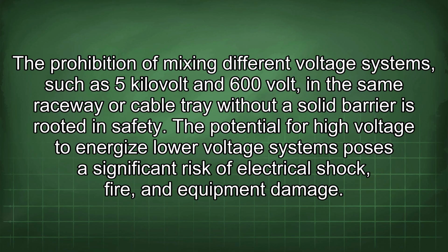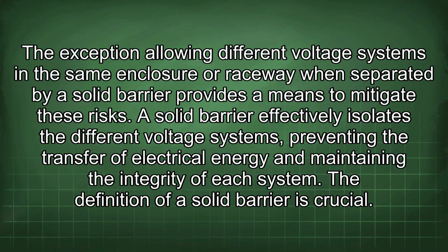The prohibition of mixing different voltage systems, such as 5 kilovolt and 600 volt, in the same raceway or cable tray without a solid barrier is rooted in safety. The potential for high voltage to energize lower voltage systems poses a significant risk of electrical shock, fire, and equipment damage. The exception allowing different voltage systems in the same enclosure or raceway when separated by a solid barrier provides a means to mitigate these risks. A solid barrier effectively isolates the different voltage systems, preventing the transfer of electrical energy and maintaining the integrity of each system.